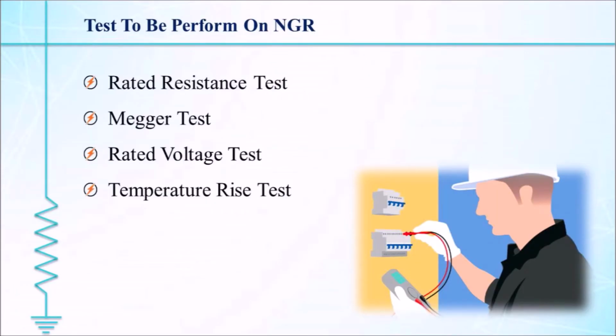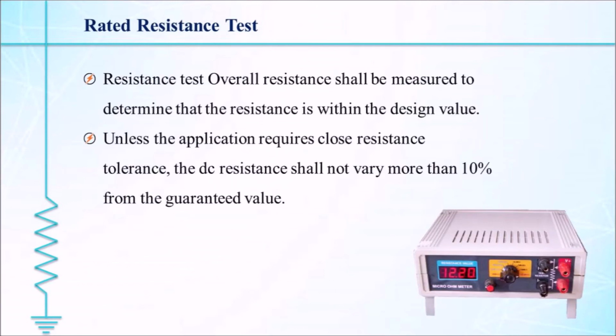To ensure the quality of the NGR, some tests are performed on it, which help to ensure that this device will work very well at fault condition. Those tests include the rated resistance test, Megger test, rated voltage test and temperature rise test. These are the main tests which need to be performed compulsorily on the NGR before installing. Now we will see all the tests one by one.